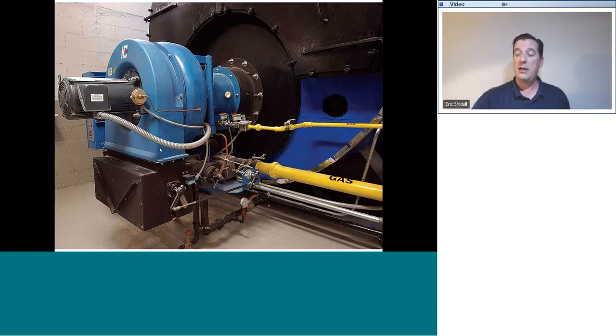First thing to realize is the combustion air is being drawn in underneath in this example. And there's a damper in there controlled by this arm, which is connected by this linkage to this arm, which is connected to this rod here, which is connected by a series of linkages to some other stuff. This one right here is our oil fuel line. You can see that black line there. That's our oil fuel line.